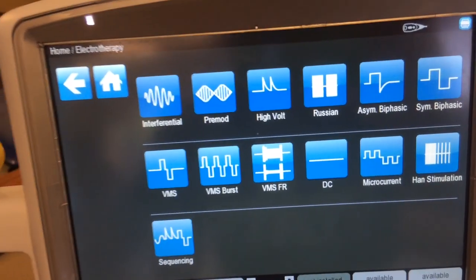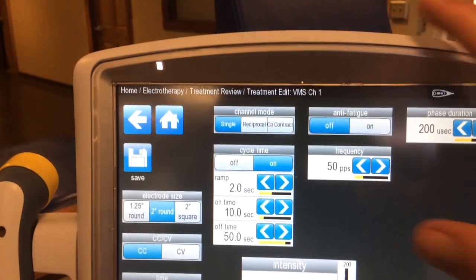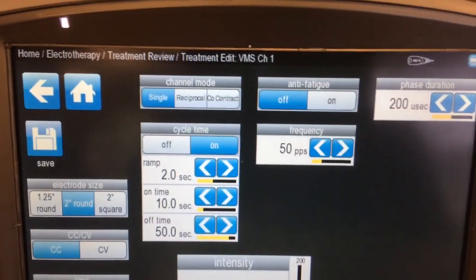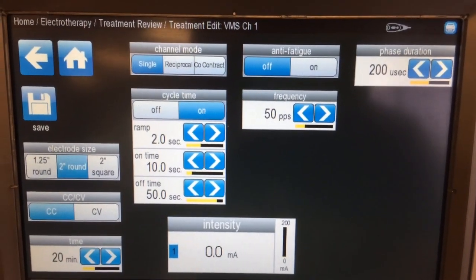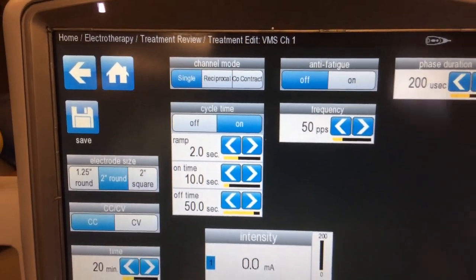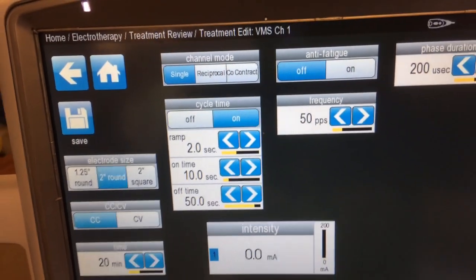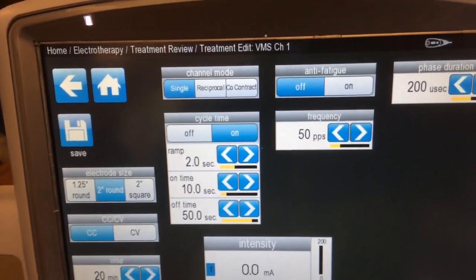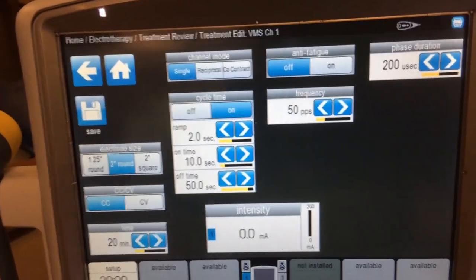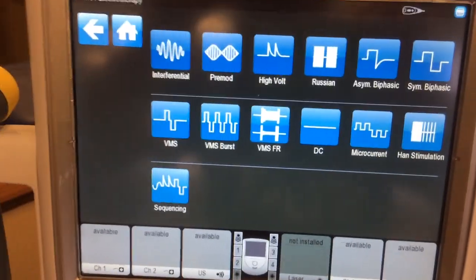VMS is very similar to Symmetric Biphasic — it's just more comfortable. It can be used for muscle contraction or for biofeedback to check muscle contraction. It's also similar to Russian but is a more comfortable version because you can change the phase duration in addition to the frequency. VMS is essentially the same as Russian or Symmetric Biphasic configured for muscle contraction biofeedback via a biofeedback lead.